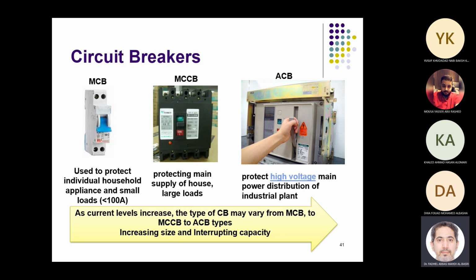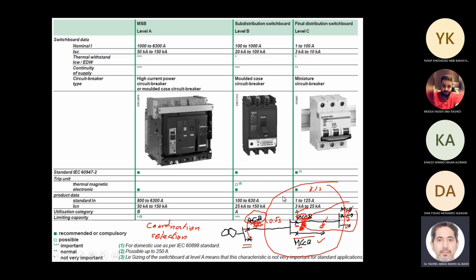And if you want to compare them by their breaking capacity and current rating, MCBs or miniature circuit breakers are rated up to 100 ampere, while MCCBs can go to thousands of ampere, and the ACB can go to 6,000-something ampere. As for breaking capacity, what's the maximum current this can break safely without being damaged, this can go up to, let's say, 10 kiloampere, while the MCCB can break fault current of 100 kiloampere, and this can go to, let's say, 150 kiloampere. What makes one break higher current than another all depends on the arc quenching mechanism.